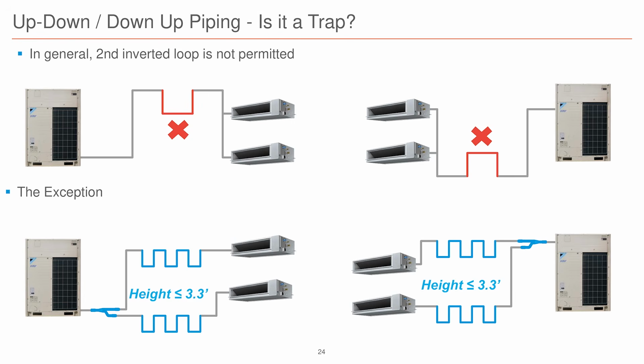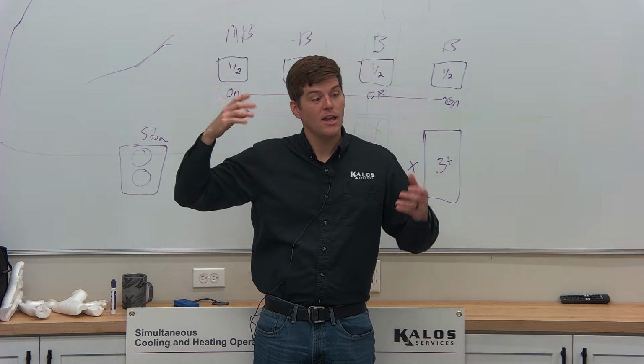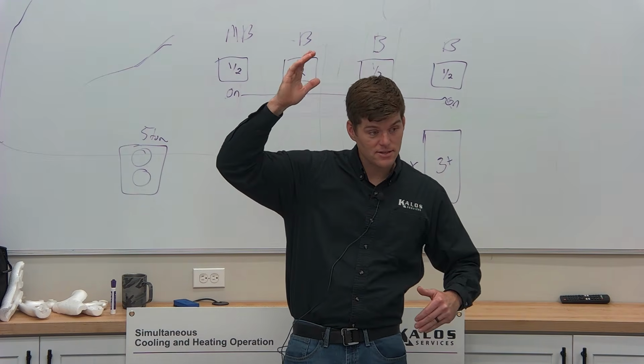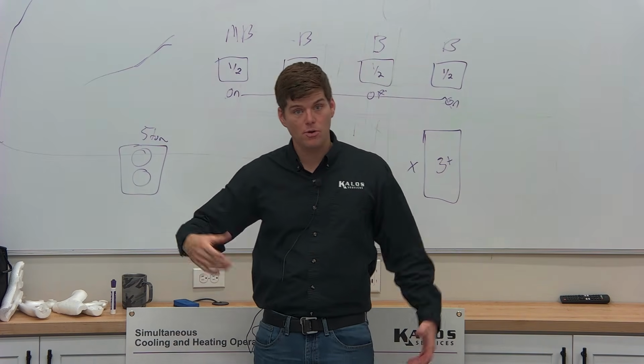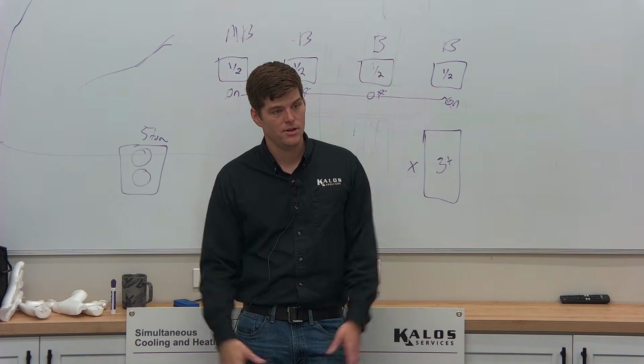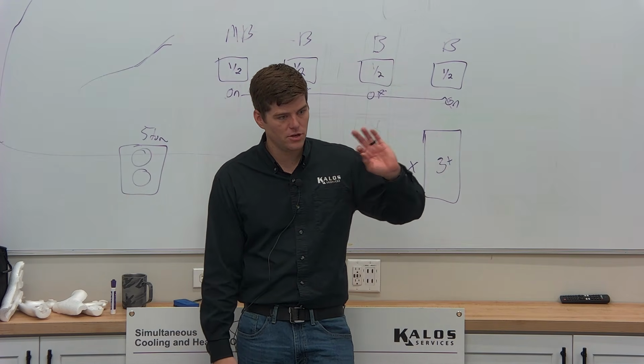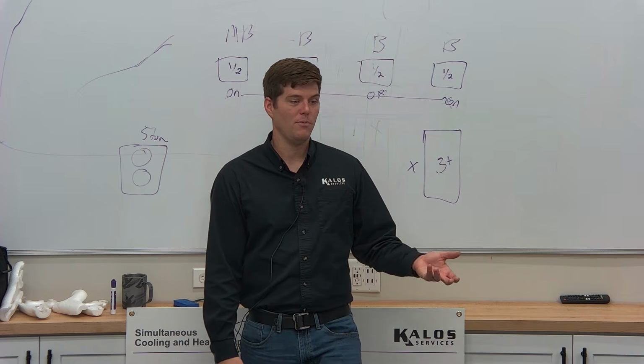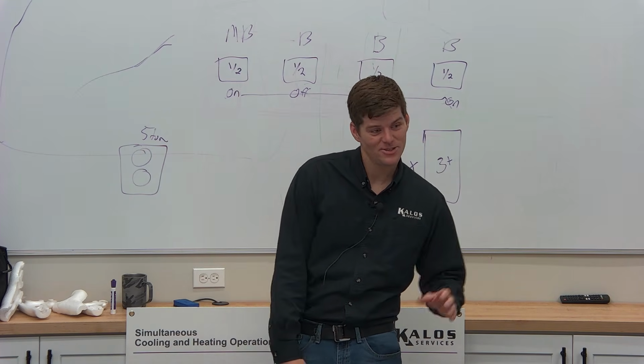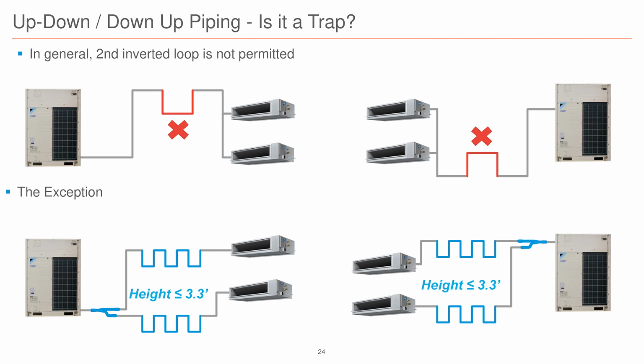We're going to simplify it. Traps, just don't do them. This isn't the 1950s. We're not dealing with R22 anymore. This isn't POE oil. This is PVE, polyvinyl ether. It doesn't require the same trapping rules that you would normally find on risers or distances. The system has the ability to overcome that height distance as long as you're within the design parameters, which I'll show you. There's a program where we put all these numbers in and it says, no, you can't do it, or yes, you can do it. You don't have to be a rocket scientist or understand the extreme complexities of these systems. You just have to know how to measure pipe with a tape measure. That's it. Well, and write it down. That's also the other part that everybody forgets. You don't need traps. Avoid traps. And the reason we talk about avoiding traps is that beautiful picture that I drew you earlier about turbulence and oil.